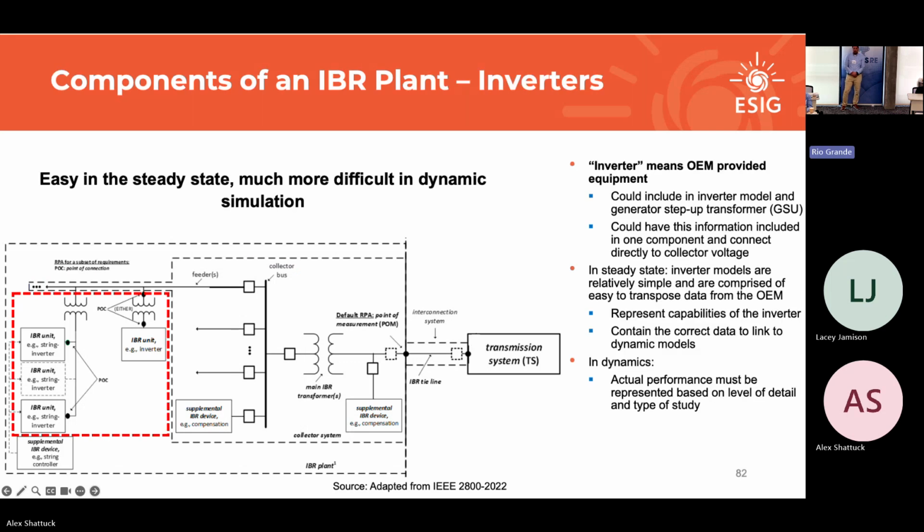The inverters, the fun piece of the IBR plant. When I talk inverters, I mean everything the OEM provides, which might be more than an inverter. Could be the inverter and the generator step-up transformer, the inverter step-up transformer, just because that's the equipment the OEM, the manufacturer, is responsible for, so I put them all in the same category. So you may see two different representations.